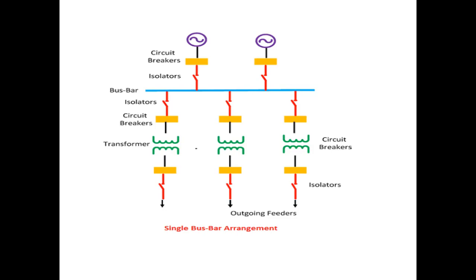Disadvantages of the single bus bar scheme: if the single bus bar fails, discontinuity will happen; it is difficult to perform maintenance; and the bus cannot be extended without completely de-energizing the substation. You cannot extend the bus bar without disconnecting supply. Despite these disadvantages, where economically justified, this bus bar scheme is considered.